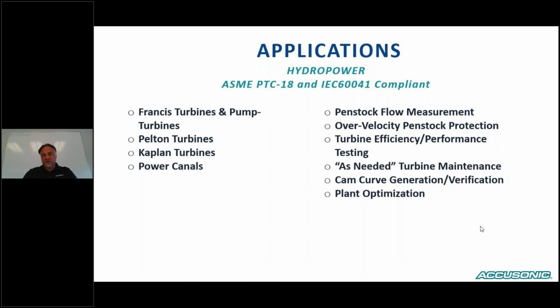And then the nice thing about this technology too is you can use it for plant optimization. So if you have a plant that has 4 units, you can actually compare unit 1 to unit 4, unit 2 to unit 3. You can determine which one's the most efficient unit, which one's the least efficient unit. So you can determine which one's my first one on, last one off, or last one on, first one off.